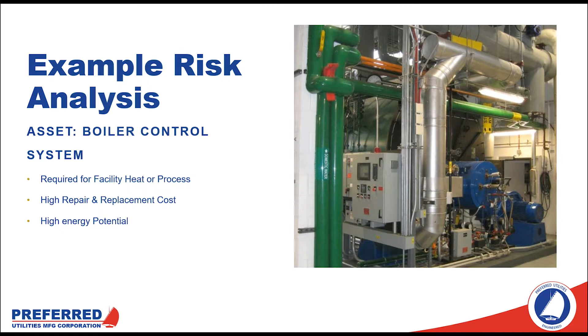To start the risk analysis, we'll do a simple analysis for physical threats. Looking at our boiler controls in the center of the circle, the first line of defense for those controls are your application security features. With the boiler control system, that's things like your operating limits, high steam pressure switch, high water temperature switch, low water level switch—all these interlocks that physically prevent the system from operating if one of these switches isn't working or is in a trip condition.